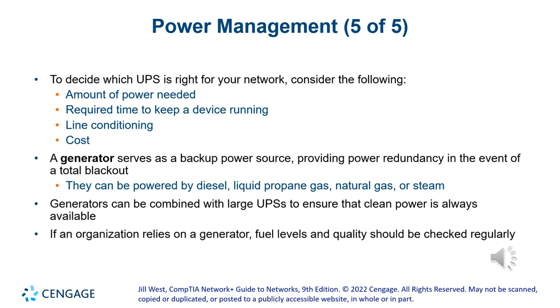So many times on those large UPSs for a data center, all you want is the UPS to hold for a few minutes. 5 minutes tops. All you want is time for that generator to kick in automatically, rev up the speed, get power and start putting power into your system. So now your input power is restored, right? And most likely there will be an automatic switch so that when the FPL input power goes off, it will go into generator, and then you start receiving the generator power. But the switch should be quick.